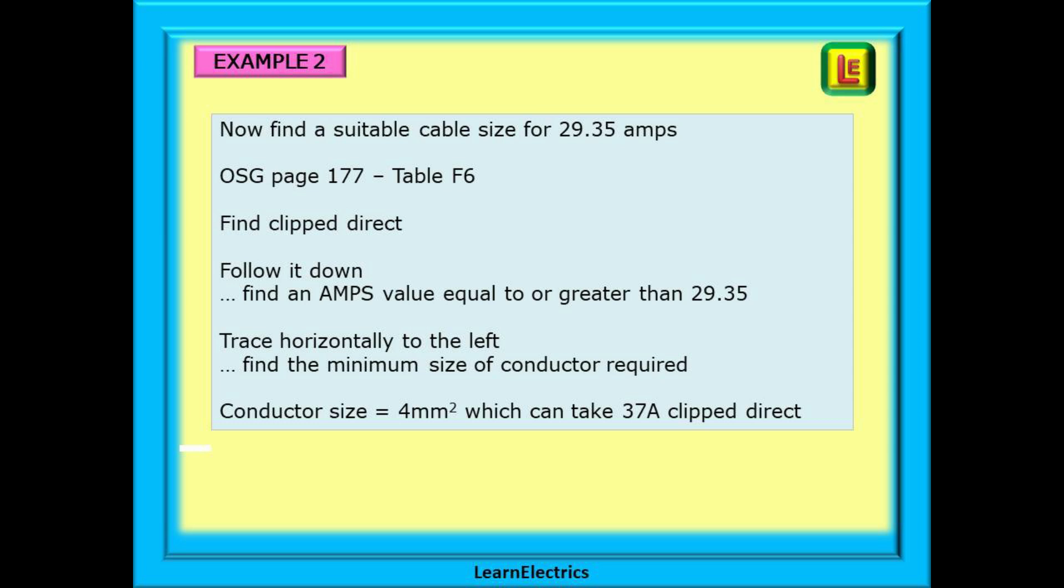Now find a suitable cable size for 29.35 amps. Look in the on-site guide on page 177 at table F6, find clipped direct, follow it down, find an amps value equal to or greater than 29.35 and trace horizontally to the left and you will find the minimum size of conductor required. In this case, the conductor size is 4mm which can take 37 amps clipped direct. Our chosen cable should be 4mm twin and earth.